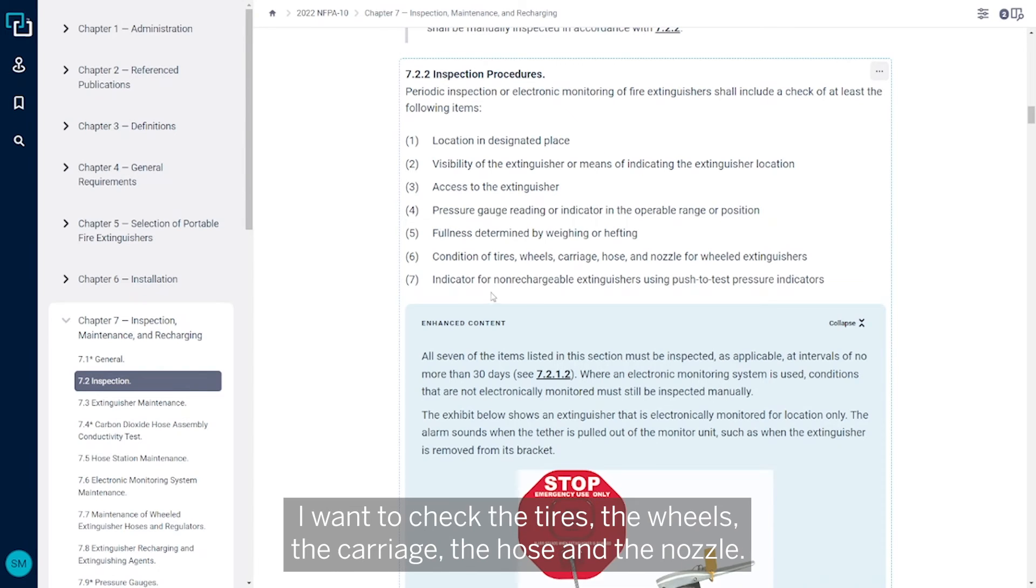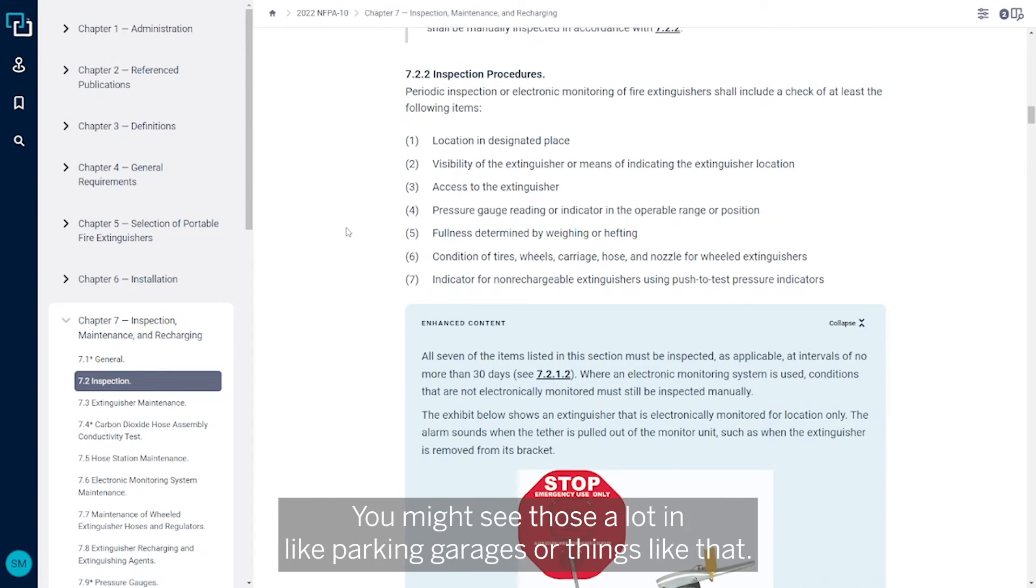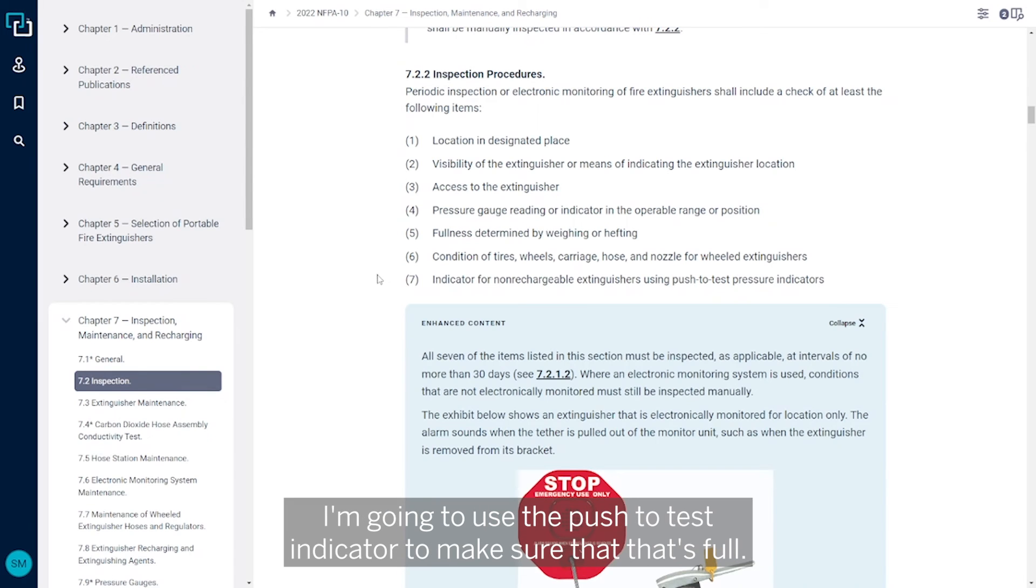And then if I have a wheeled extinguisher, I want to check the tires, the wheels, the carriage, the hose, and the nozzle. Again, most people might not necessarily have a wheeled fire extinguisher - you might see those a lot in parking garages or things like that. And then finally, if I have a non-rechargeable fire extinguisher, I'm going to use the push-to-test indicator to make sure that it's full.